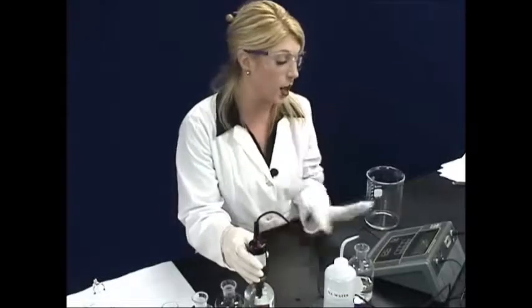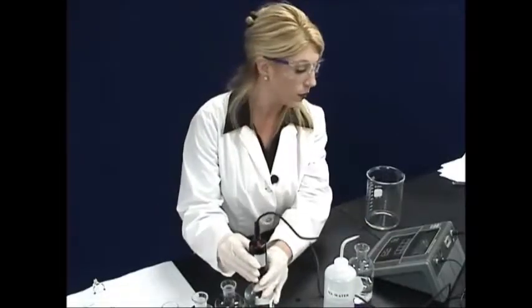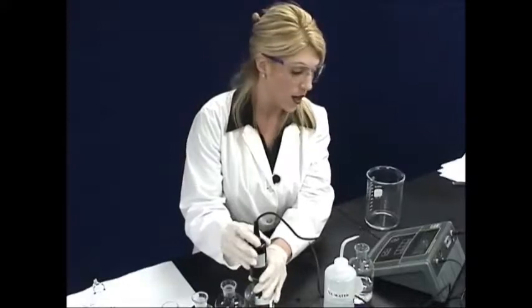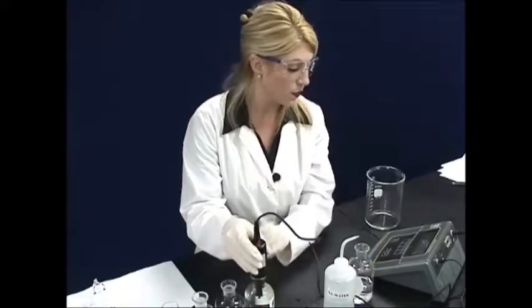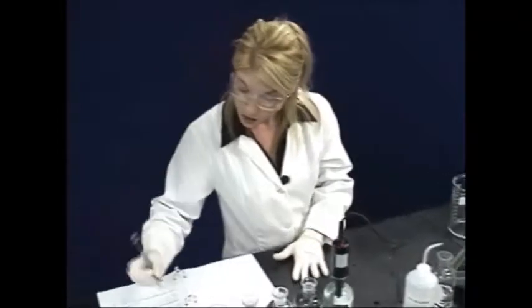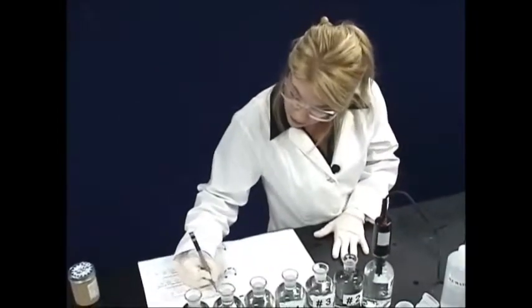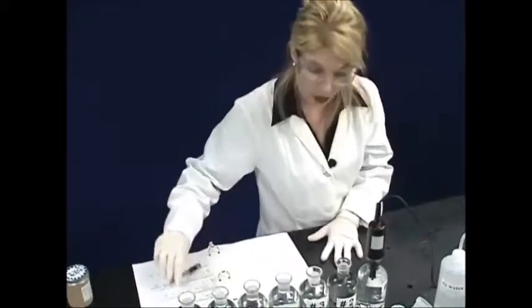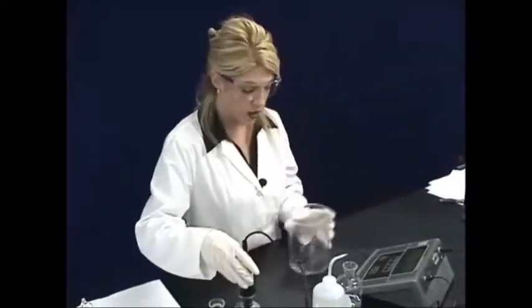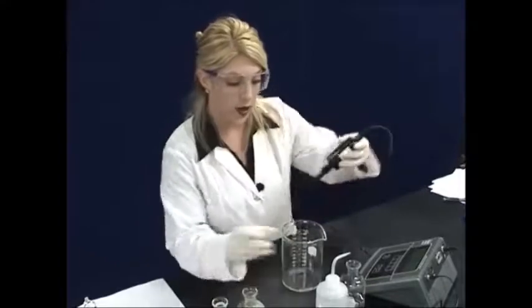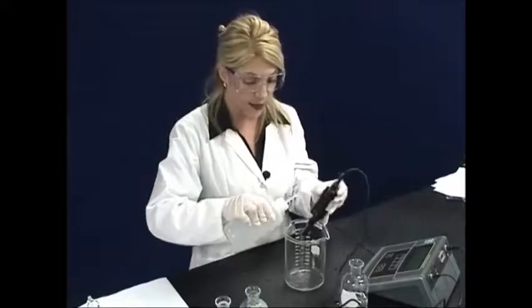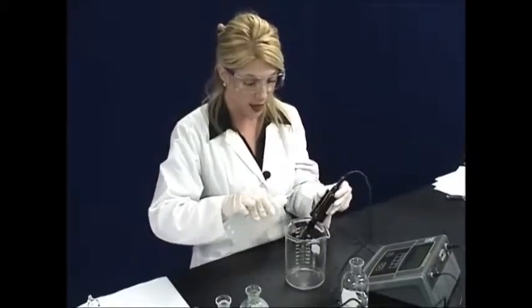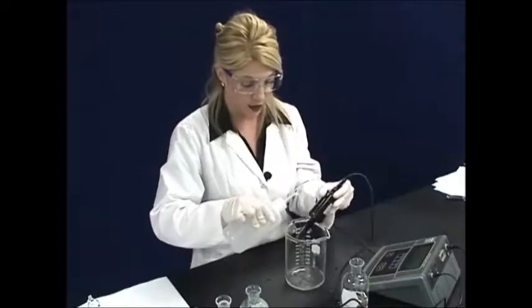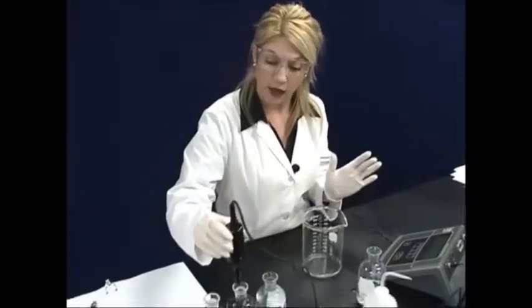We'll wait until our DO meter beeps to get the reading. Turn off the stir and record the reading. Ours is 8.98. Next, you will take the probe and will want to clean it with deionized water. So use a deionized water squirt bottle, clean the probe. This will help us to avoid any cross-contamination that could occur while we're doing our readings. After you've cleaned the probe, you will place it in the second bottle to be read.